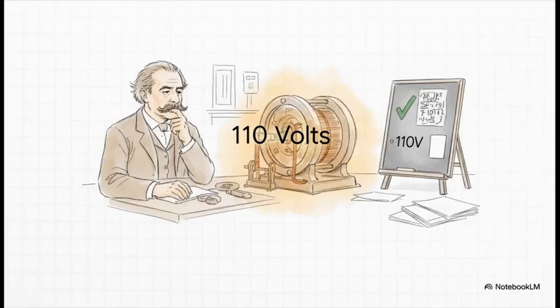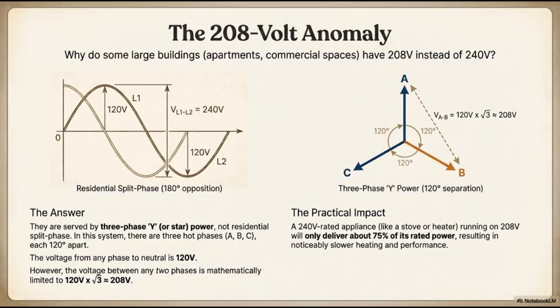And the I²R loss isn't the only manifestation of this forced 120-volt constraint. To see a perfect mathematical proof of compromise, we just need to look at the 208-volt anomaly. It's often rounded from about 207.84 volts, which you find in commercial or apartment buildings served by three-phase Y or star power. This shows how our reliance on the 120-volt phase-to-neutral constraint creates systemic operational compromises.